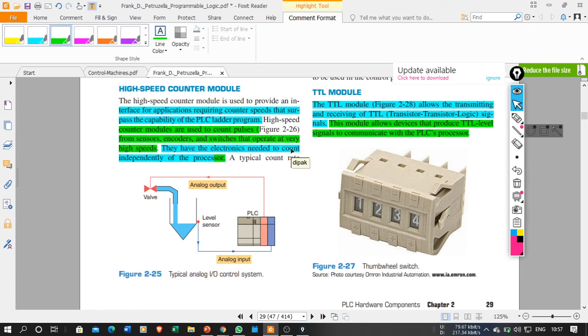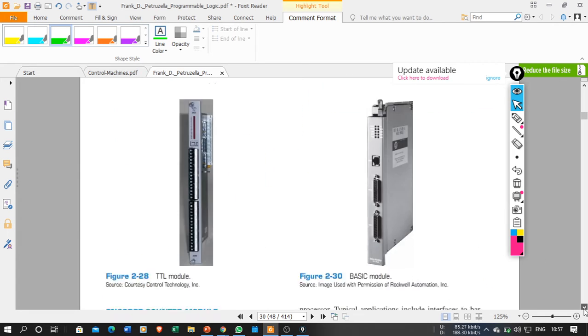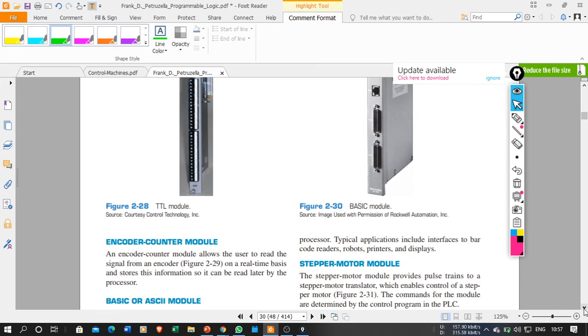If the PLC's operating voltage is 5 volts and the device's operating voltage is 3.5 volts, then communication will not be established, because 3.5 volts is 1 for the device, and the PLC will read 1 only at 5 volts. The PLC will not understand what the device is communicating. So what I have to do is maintain the voltage level of my field devices and the PLC at the same level. So I need to use the TTL modules over there, or the signal conditioning circuit over there.